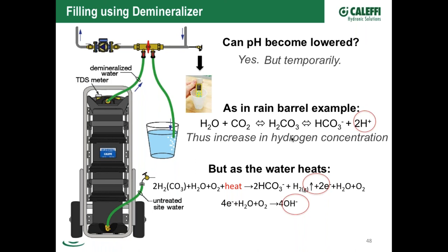However, in a boiler, what happens—I'll skip the detailed equations—is that when you heat up carbonic acid, it reacts with H2O, oxygen, and heat, and basically increases your hydroxide. So your pH then starts to increase, as a result of driving off hydrogen, back not only to 6 or 7, but as indicated, typically around 8 on most systems. There are a lot of factors, but the hotter your system is, the quicker it gets to that neutral pH level of around 8. So the answer to the question about being concerned over low pH in your hydronic system is typically no, because over time that pH will rise into that safe zone that all metals like—what we call the happy zone of about 7.5 to 8.